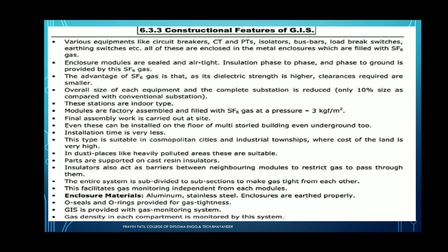These substations are indoor substations. Modules are totally enclosed. Modules are factory assembled and filled with the SF6 gas. Gas at a pressure of 3 kgf per centimeter square. So this is the pressure of the gas which is filled inside that cylinder. Final assembly work is carried out at the site. Even this can be installed on the floor of a multi-storey building, even underground also. Installation time is very less.